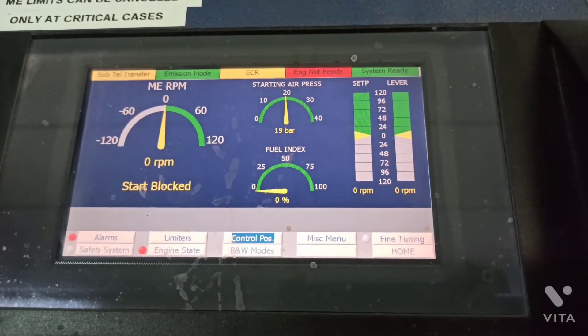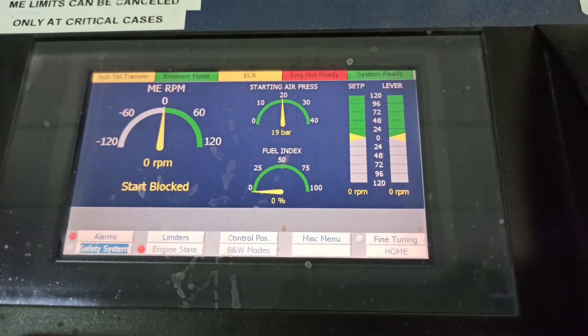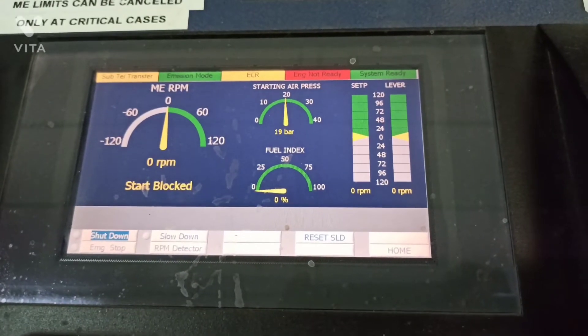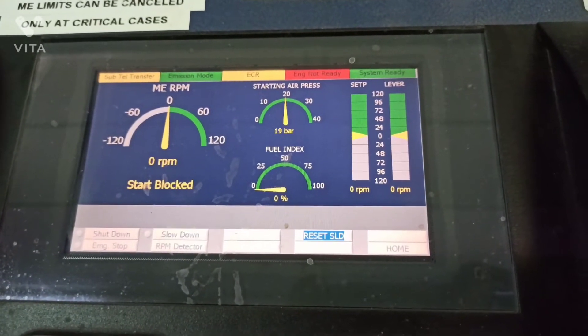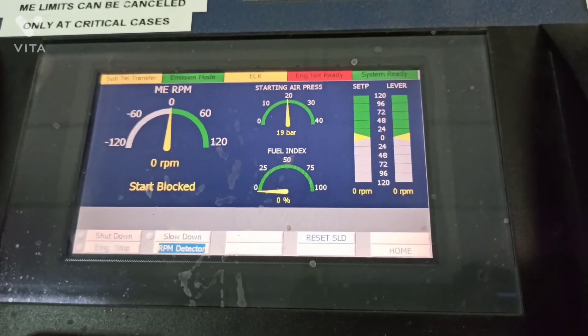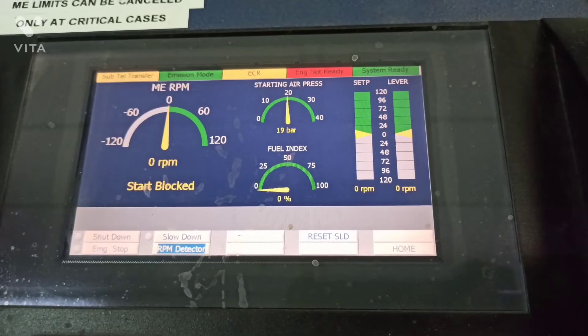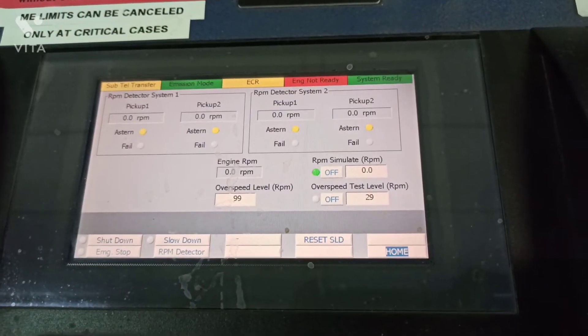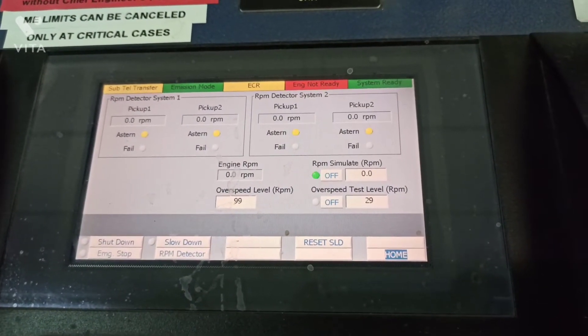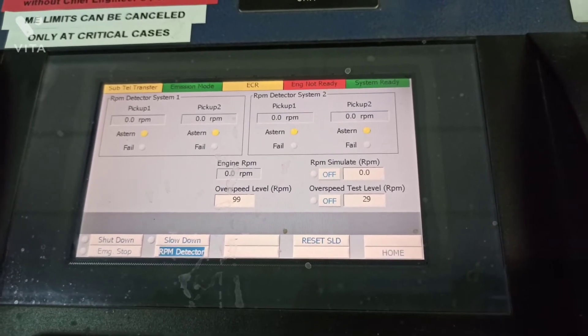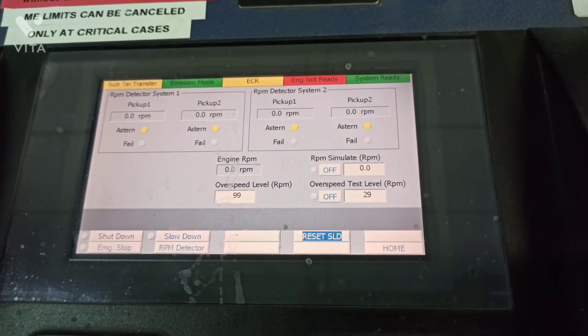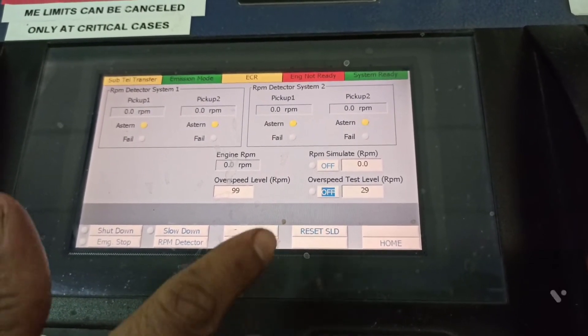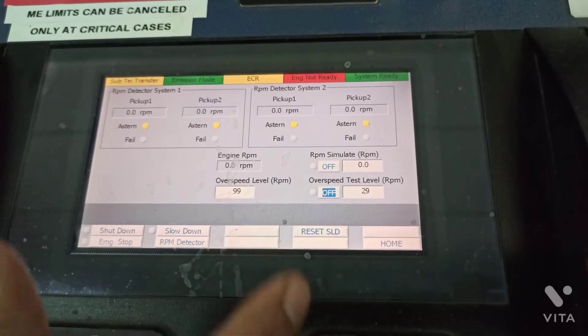Then you need to select the safety system. In the safety system, you need to select RPM detector. In the RPM detector, you will see over speed test level and over RPM simulation. First, you need to turn on the over speed test level.